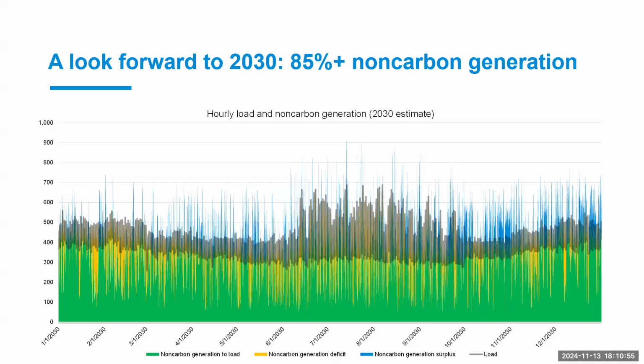This shows the same thing over the full year, just to show this isn't cherry-picked from one day. With 1,100 megawatts of non-carbon generation and load between 400 and 700 megawatts, the blue spikes show when there's too much, the yellow shows when there's not enough, and the green is where non-carbon generation meets the load. It happens repeatedly, probably a few times every day.